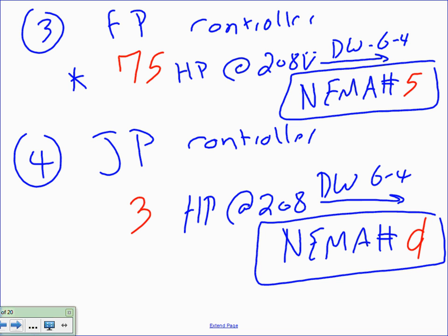Now, could I use a soft start on these babies? Yes, I could use a soft start. Should I use a VFD? Would it make sense to use a VFD in a fire pump? Do you really want to speed control the fire pump? I mean, I don't know, maybe there's something that I don't know. But soft start, really good.